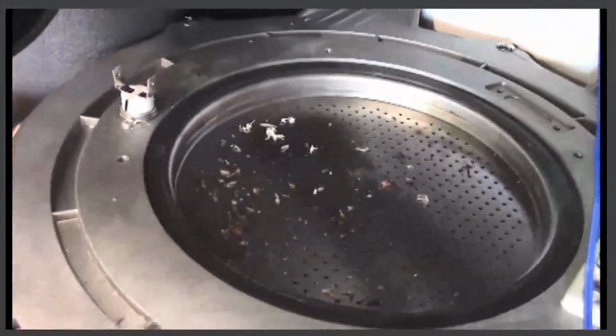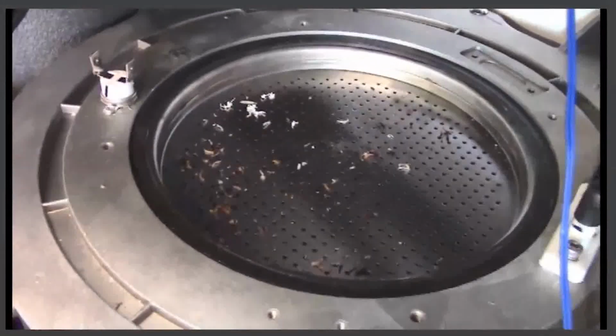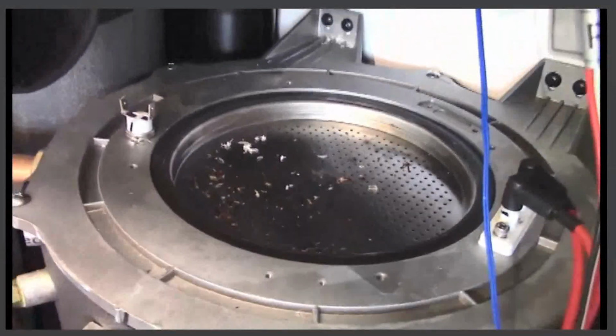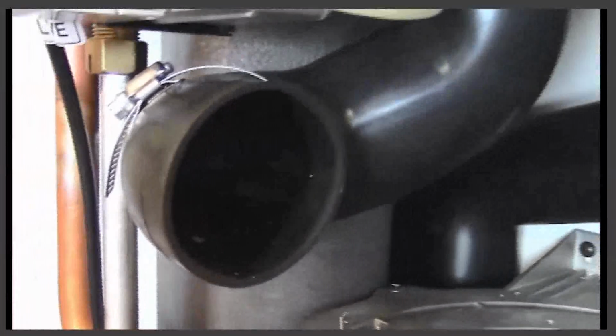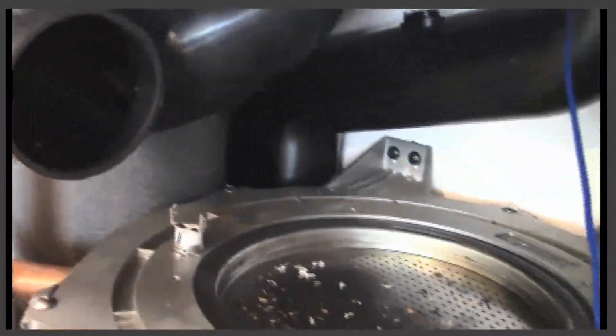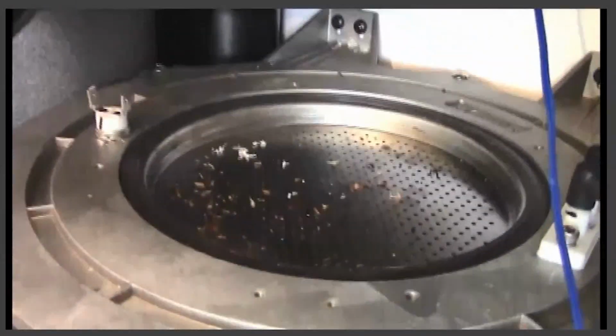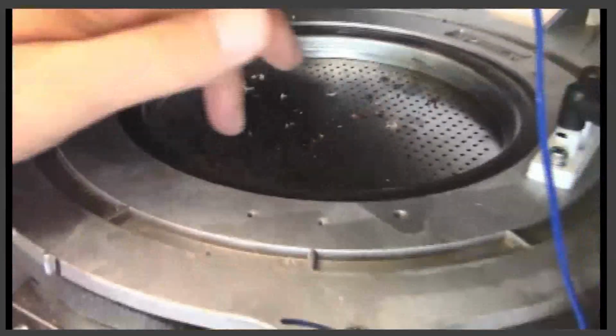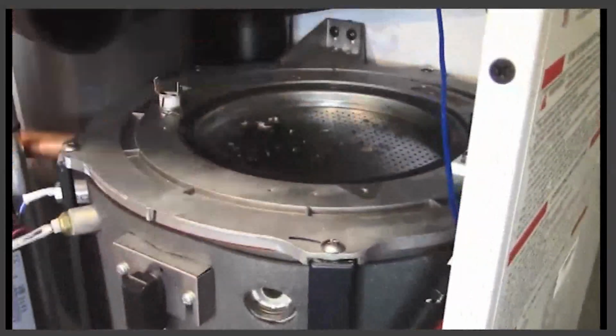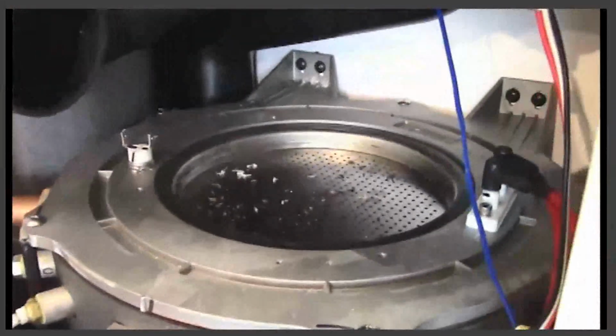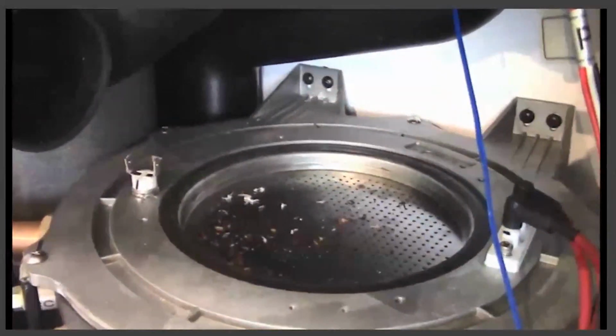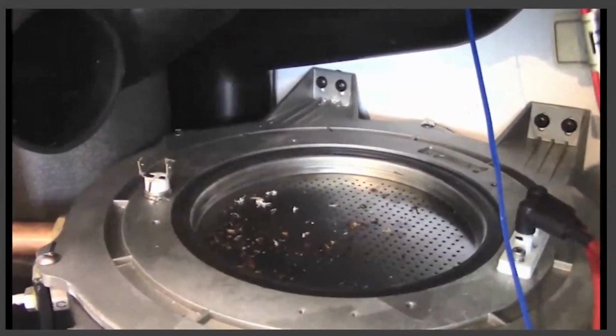Now, I want to mention to you, a lot of times contractors are not cleaning their PVC shavings or PVC pipe when installing the combustion air intake. Where does that end up? Well, that comes down our combustion air boot through the blower and the top of the burner. Ken will pull the burner and then we'll get a look at that, but that will plug up your burner, and this is a good example.